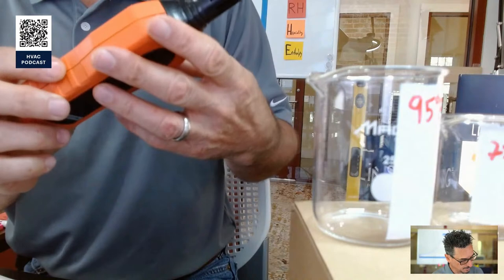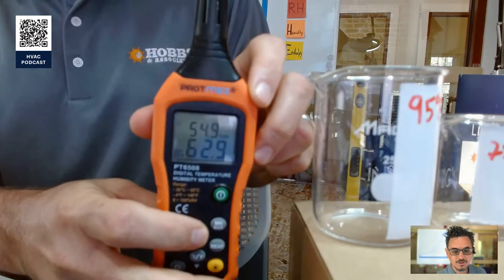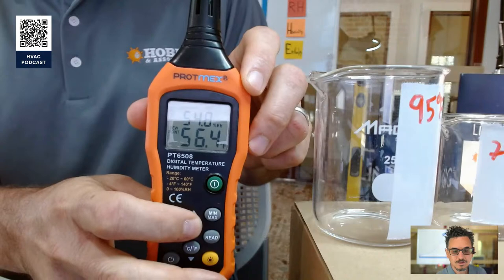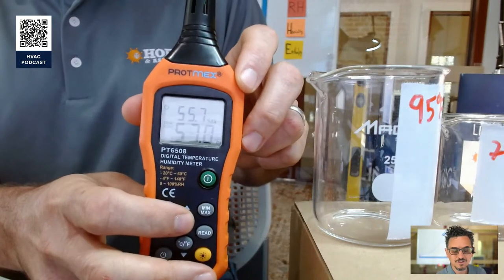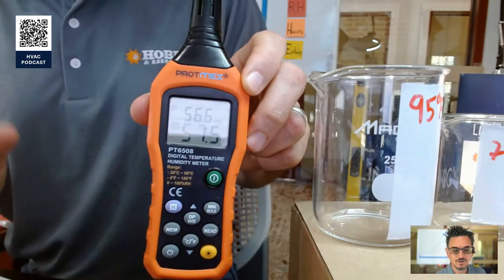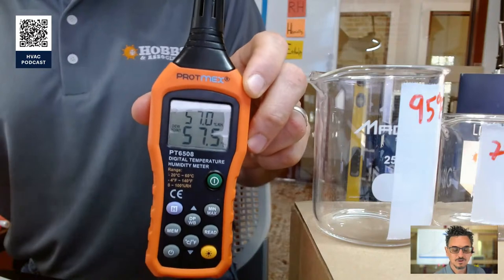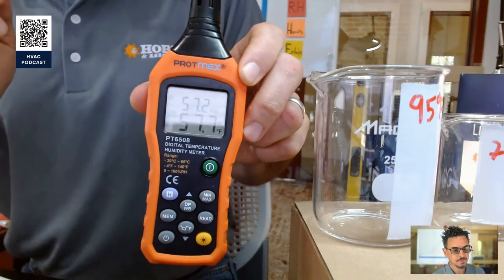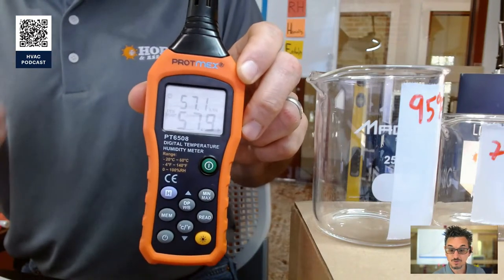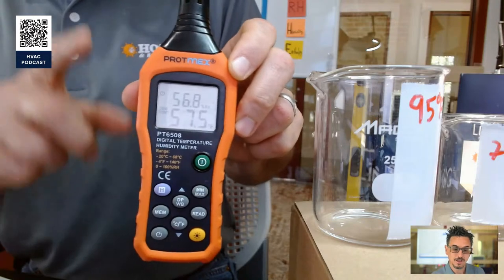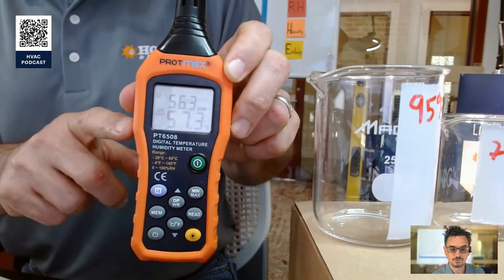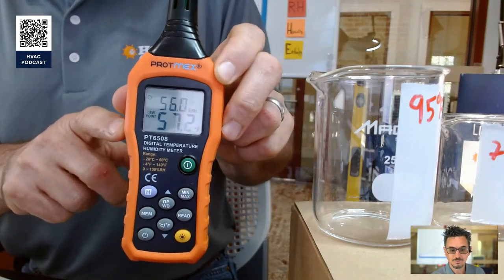Okay, so dew point. Now I have an experiment here. So for dew point, we're going to go back to our meter. The dew point in this office is 57-ish, 57.5 degrees. Now, what dew point means is it's the temperature at which moisture will be pulled out of the air. So anything colder than the dew point of this space will condense water on it.